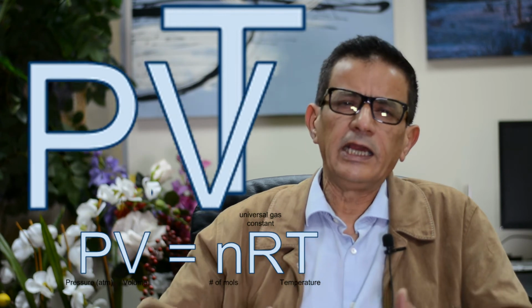The simple equation which describes the physics of the gas is PV = nRT. P is the pressure, V is the volume, n is the number of moles, R is the gas constant, and T is the temperature. When T increases, the pressure and the volume of the gas will increase. And when the temperature increases significantly, as in fault conditions, the pressure and volume of the gas will increase. If it is not resolved, an explosion will happen, and this is very dangerous. So the pressure relief valve provides a route for this extra volume and extra pressure inside the transformer. It provides relief, and that's where the name comes from, and consequently protects the transformer from explosion.